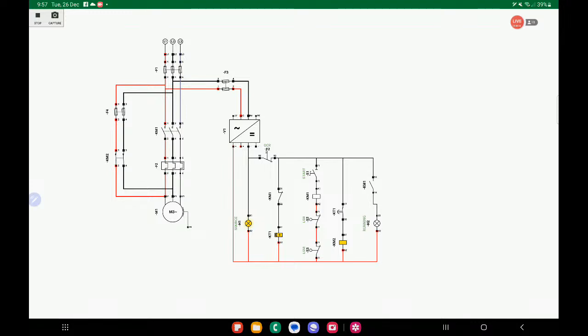which eventually they didn't notice, no, and the control panel doesn't have an indication light that the space heater is running, so they didn't notice it, and then there is no heating onto our electrical motor. The ship is sailing into a cold area, so moisture went in, winding got damaged. We didn't have an electrical motor then onto one of our vessels, so we needed to order an immediate requisition so that we can replace the electrical motor. So this is one of the problems. We need to put an indication light that the space heater is running.